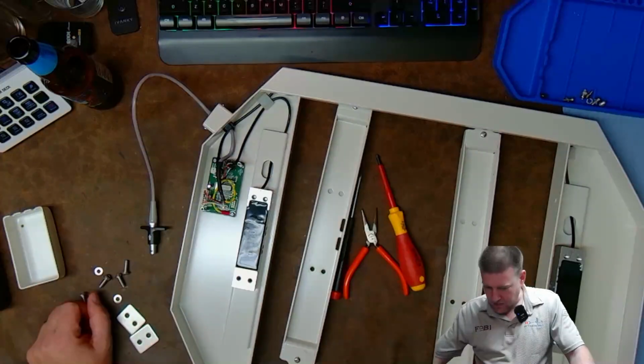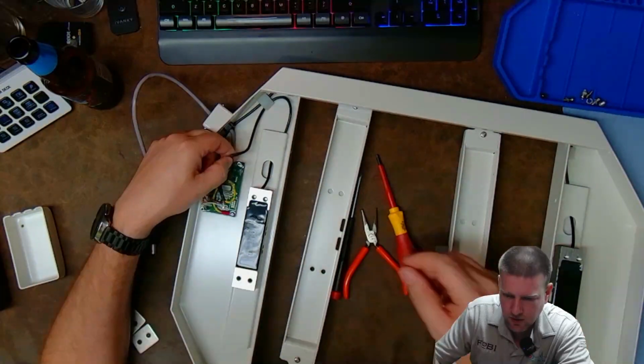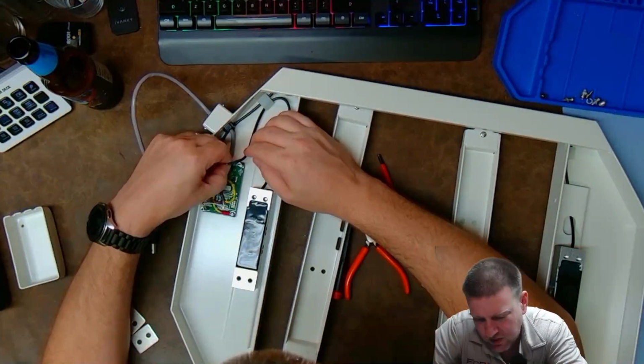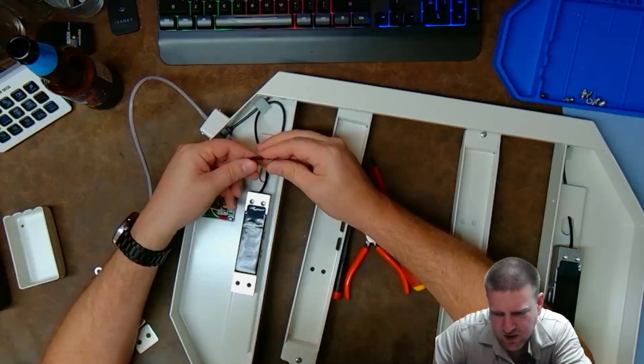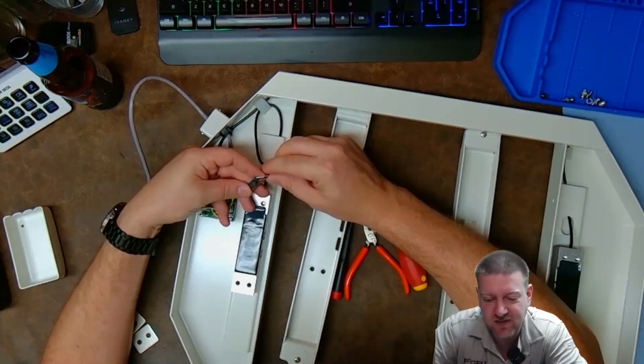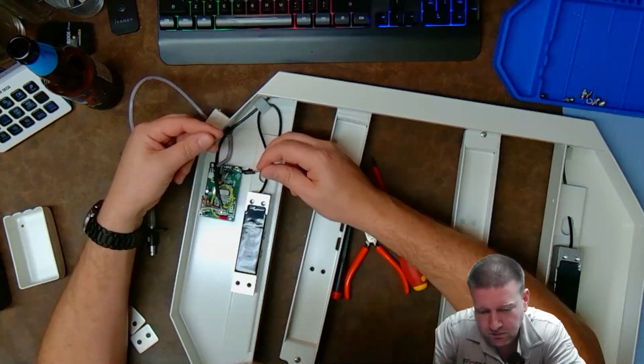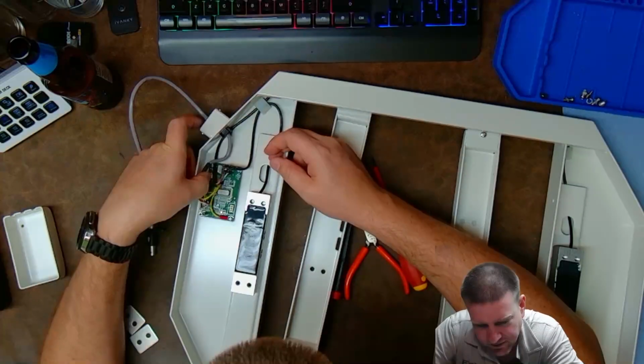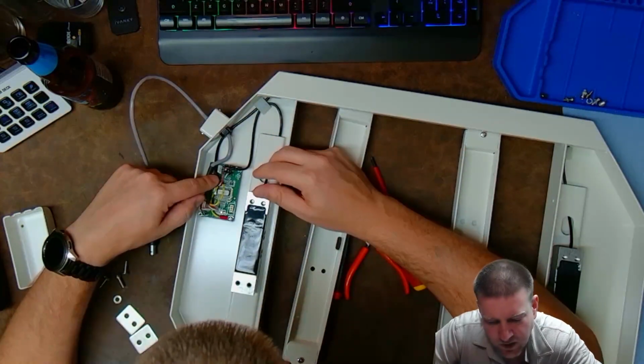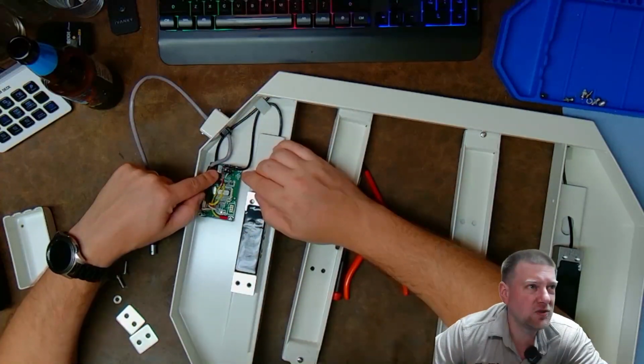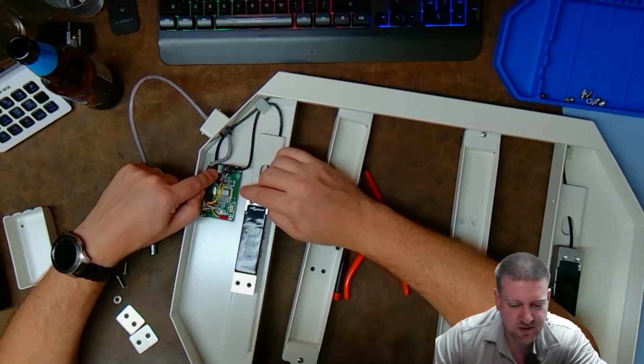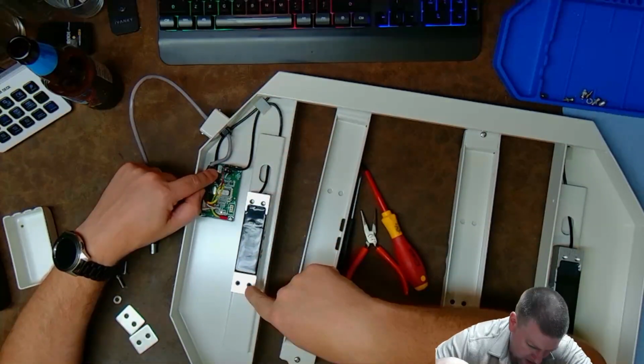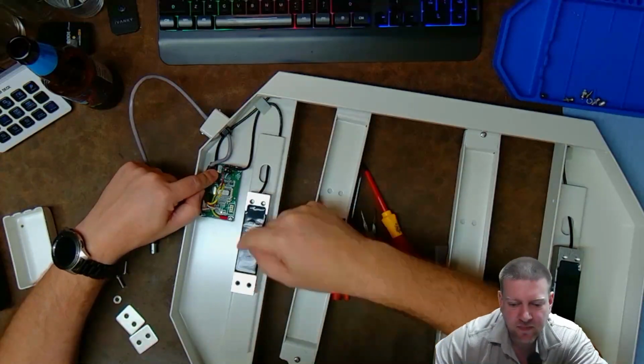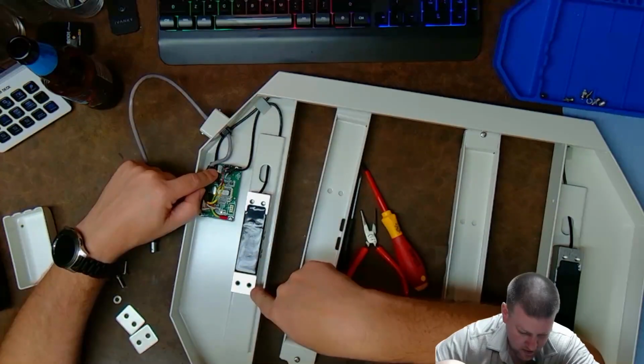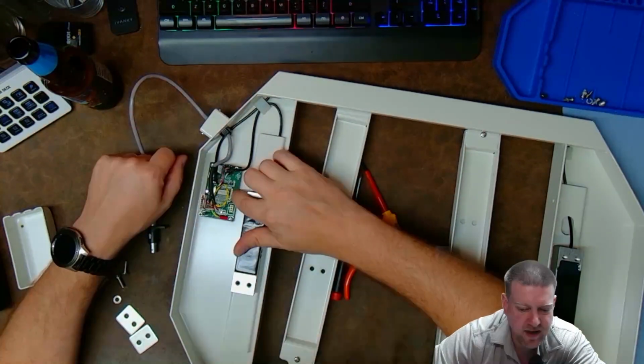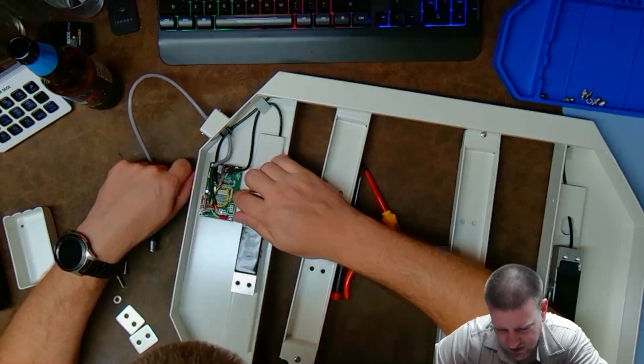Okay, so I would be very curious if these are repairable. Reason being is you have these little connectors right here, which you can buy. You can get these little connectors, and you would just repin it, and then you would have to do a calibration. And I'm guessing that this guy right here is going to set your voltage to your load cells. So this is how you calibrate the voltage, probably according to their specs. You're probably going to have to measure that right here. And then the 16.04, I don't know if that has to be programmed or not. That's interesting. I'll have to look that up.